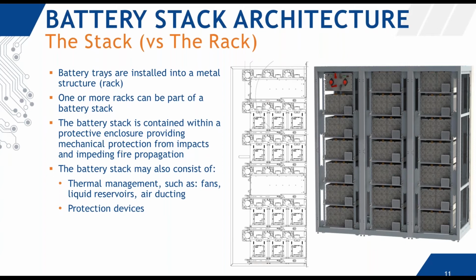And of course, the battery stack can also consist of thermal management. So those would be things like fans, liquid reservoirs, air ducting. You can get pretty integrated, as well as the protection devices. So as mentioned, the stack switchgear will have fuses and contactors, and that's what I'm referring to. And so this image is actually one of our configurable stacks that was designed for a customer. So it was giving them the options to remove or add modules and racks to a stack to reconfigure it for different voltages.